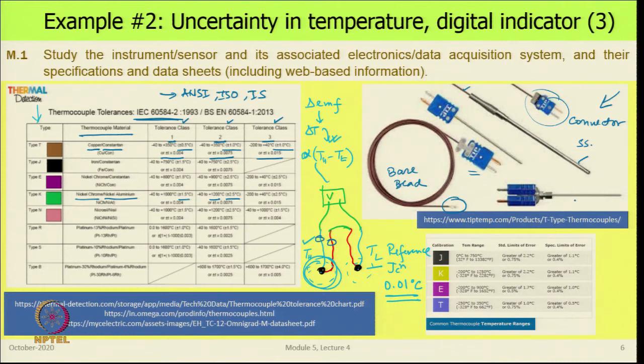And this is a configuration where you have a shield, inside that is the thermocouple, and right on top itself is the connector integral to this body. So, there are very large number of permutations, combinations that are available standard, and on top of that you can yourself design your own sensor also.